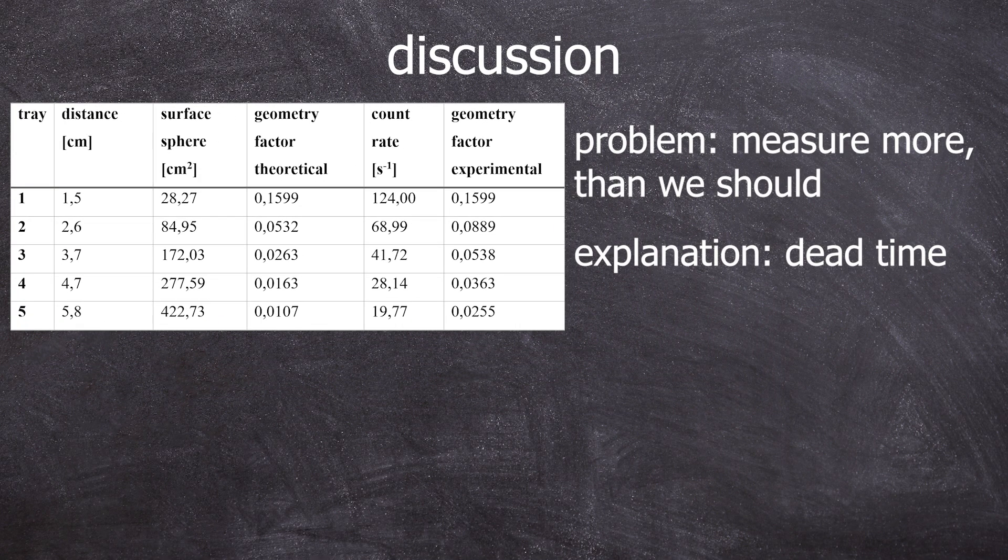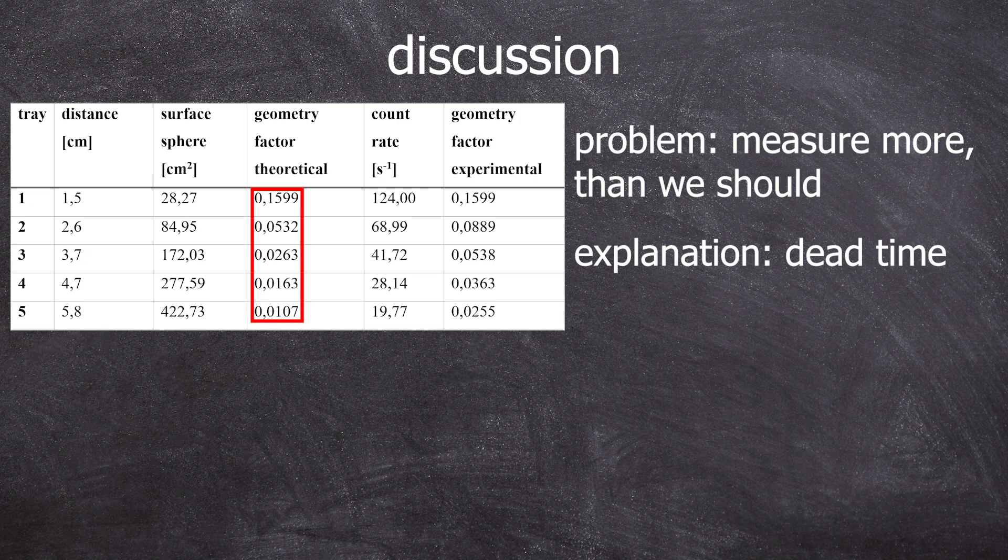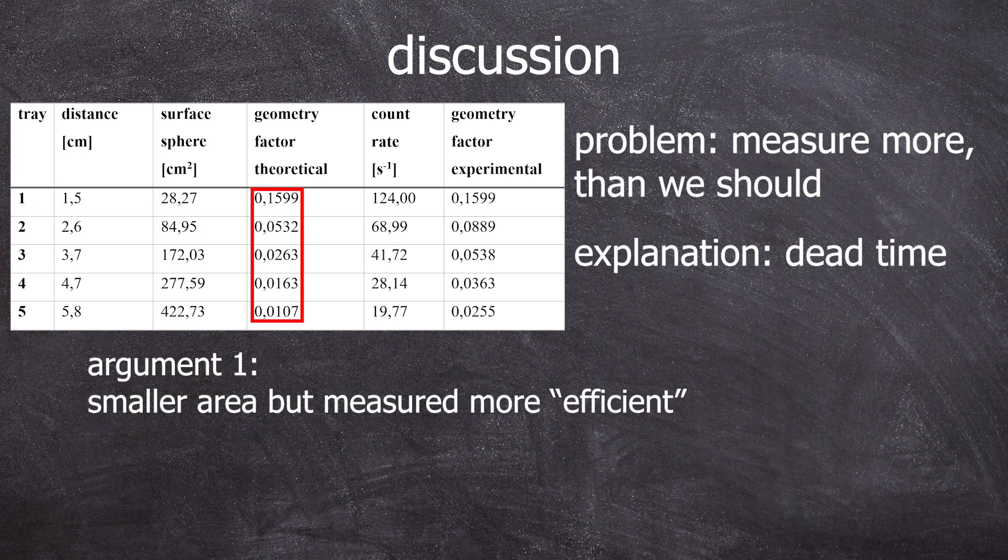At the highest count rate, you also have the most dead time. The further we move away, the lower the dead time becomes, because the count rate also decreases. So while you are covering a smaller percentage of the surface, you effectively count more of the area that you do cover, because fewer photons simply pass through the detector due to the reduced dead time. This is one way to argue it.